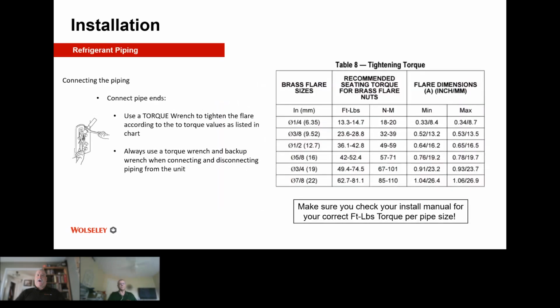Okay, let's look at refrigerant piping. When I was in school doing training on compression fittings, there was an interesting test our teacher did in the class, and he wanted to find out how good we are at tightening, doing torquing, because we all know that there are torque wrench settings in the manual, and he wanted to know if we could do it. Now, many of us guys and girls, we're very strong, and we think that we don't need to worry about what the foot pounds are, the newtons are, and we just tighten to what we think and we're close enough. We found out that in 80% of the students who did the freehand tightening, they were actually less torque than they were required in the manual.